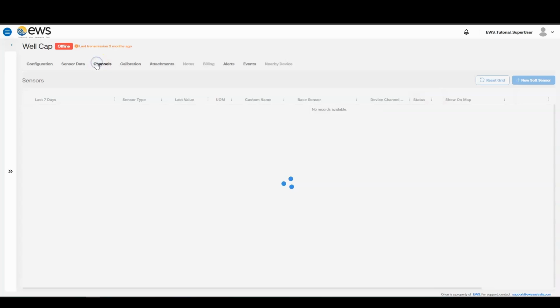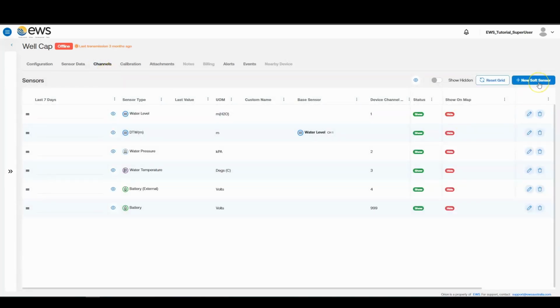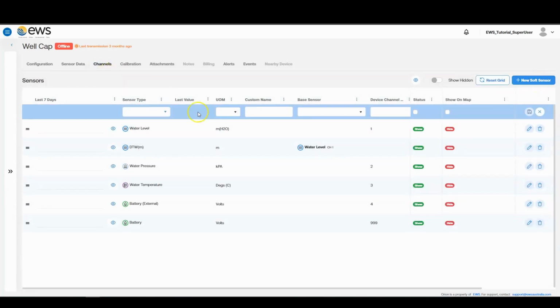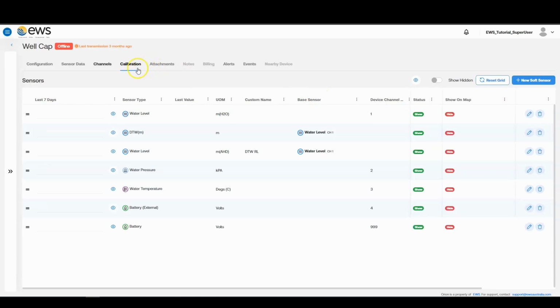Another common water level calibration is a conversion to a relative surveyed level. We'll start by adding a new soft sensor, giving it the type of water level, and changing the UOM to meters AHD. We'll call this one depth to water RL. Choose the base channel of water level, then save the channel and head to the calibration page.